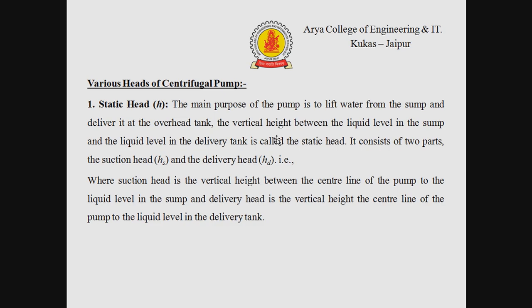So let's start. First we discuss the various heads of a centrifugal pump, beginning with the static head. The main purpose of the pump is to lift the water from the sump and deliver it to the overhead tank. The vertical height between the liquid level in the sump and the liquid level in the delivery tank is called the static head. It consists of two parts, the suction head and the delivery head.